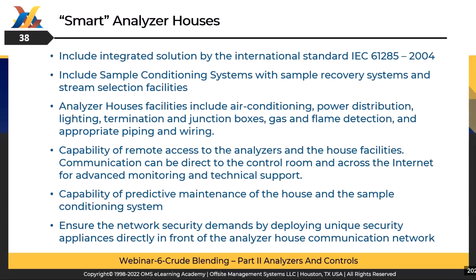Analyzer houses are actually delivered prepared and pre-wired, with all the equipment inside, with the analyzers, sampling systems, and also other utilities installed at the factory. The complete assembly is tested and shipped to the site as a single package. Most such projects are usually managed on a turnkey responsibility basis, when the same team manages the project from start to end. In such a way, site installation work is kept to a minimum.